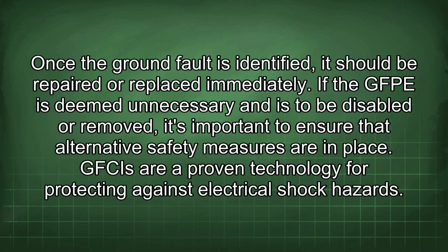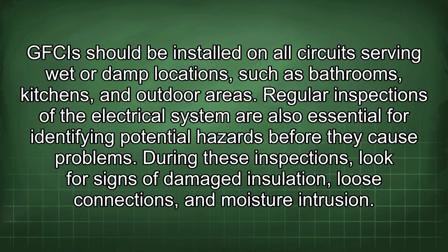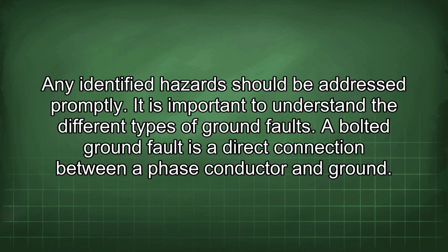If the GFPE is deemed unnecessary and is to be disabled or removed, it's important to ensure that alternative safety measures are in place. GFCIs are a proven technology for protecting against electrical shock hazards. GFCIs should be installed on all circuits serving wet or damp locations, such as bathrooms, kitchens, and outdoor areas. Regular inspections of the electrical system are also essential for identifying potential hazards before they cause problems. During these inspections, look for signs of damaged insulation, loose connections, and moisture intrusion. Any identified hazards should be addressed promptly.